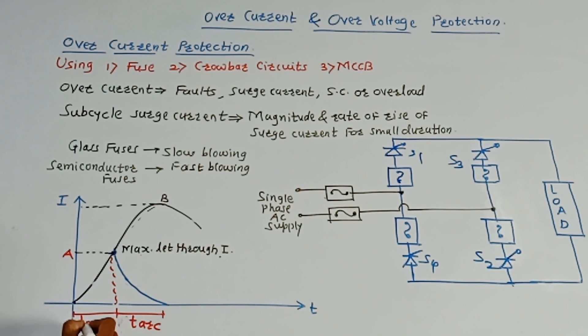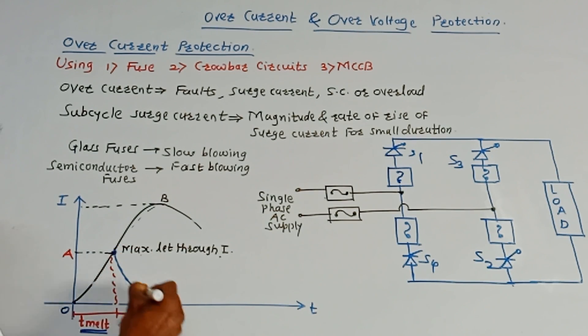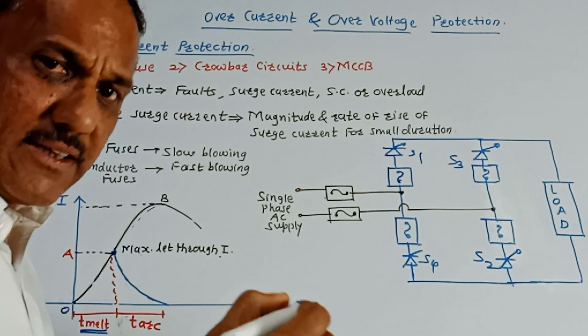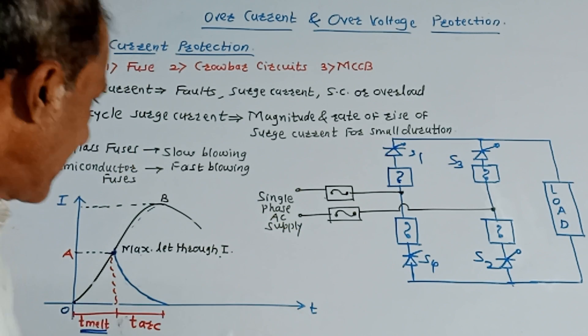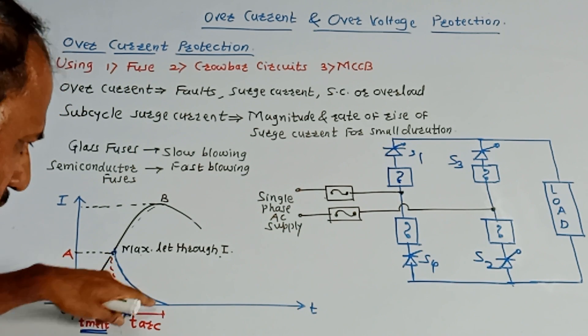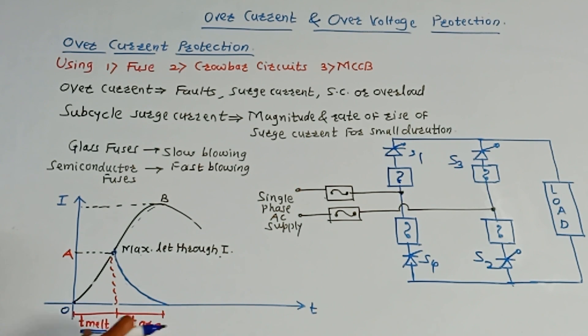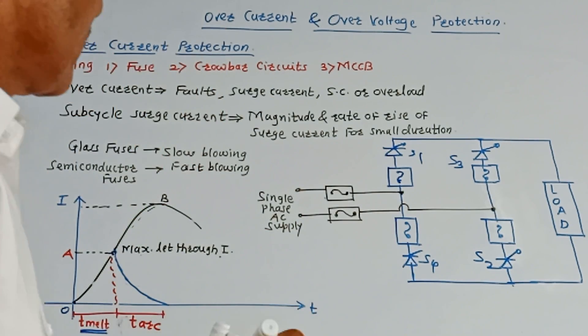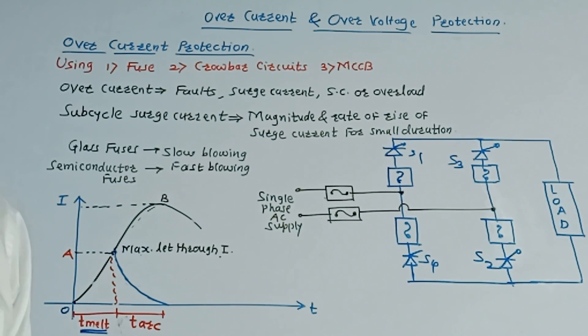Whenever the maximum let-through current is reached, this time period starting from zero is called melting time, that is T-melt. That is melting of the fuse takes place. After this, arcing takes place. Due to arcing, the current reduces suddenly, indicating the arcing takes place and current reaches to zero after some time. This total time period should be as minimum as possible. This is the overcurrent protection circuit used for power semiconductor devices.